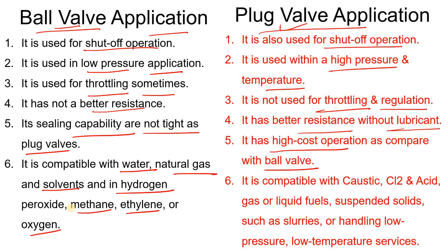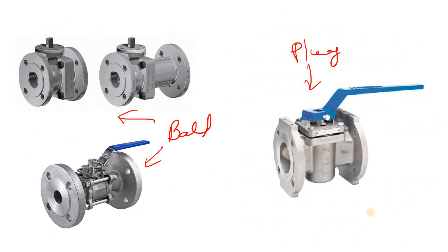The plug valve is most compatible with caustic lines, chlorine lines, and acid lines. In ball valves, when used in caustic lines, choking problems can occur. Similarly, in molten urea lines, choking problems can occur, so we prefer the plug valve there. Plug valves are also used in steam lines, suspended solids, and slurries.